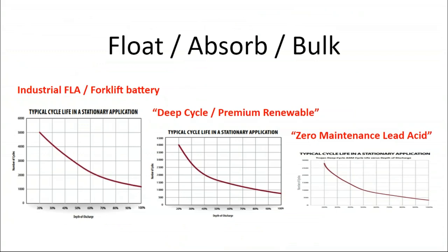Batteries have different charging stages, and these charging stages are more of a concern for industrial lead acid because industrial lead acid is an unsealed battery. Batteries, whether sealed or unsealed, when charged rapidly, produce a lot of gas. Sealed batteries cannot be charged as rapidly as unsealed batteries of the same chemistry, because a sealed battery has to contain the gas, and if you charge it too quickly, it can compromise the battery. The battery will start to bulge as the gas forces the battery shell apart.